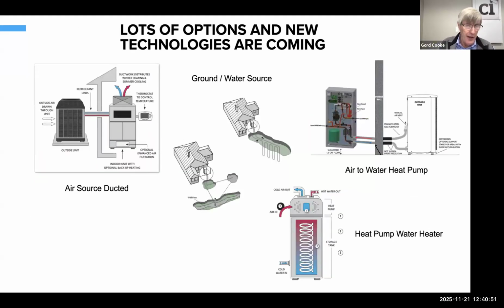We're seeing on the left air source ducted. I wanted to highlight ground source again, and on the top right, air to water heat pumps starting to come across - specifically for houses where you want in-floor heating or radiator-based, hydronic-based heating. We're starting to see products that can take heat from the air outside and bring it into the house. This has a secondary advantage: in these cases, the lines running to the house are not refrigerant-based, they're hot water and chilled water, which takes away some of the complexity of refrigeration.